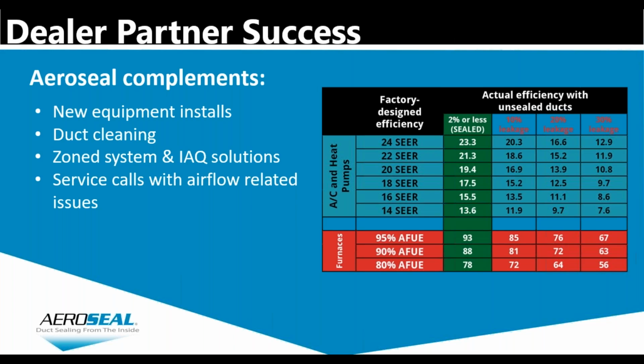gives some varied degrees. So at 10% leakage it's a 15.2 effective SEER rating, at 20%, 12.5, and at 30% duct leakage, it's 9.7 SEER rating. So it degrades quite a bit. The big thing I want to touch on is this green column here, which indicates the ducts that are sealed to 2% or less, which is effectively what Aeroseal can provide.